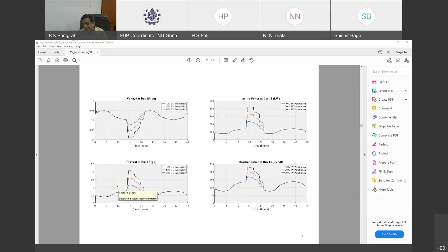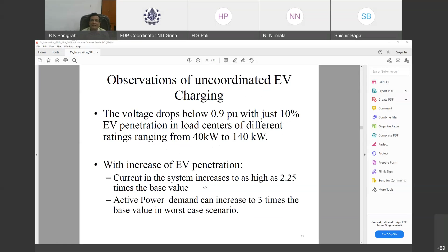So the main idea is that you have a voltage profile of 48 hours whenever there is no EV load. But once you put the EV load, the problem arises because of large EV penetration plus uncoordinated charging. So the observation of uncoordinated charging is that the voltage drops below 0.9 per unit with just 10% EV penetration in load centers ranging from 40 kilowatt to 140 kilowatt. Similarly, the current also increases as high as 2.25 times, and the active power demand also increases to 3 times. So this is one of the studies which we have done.